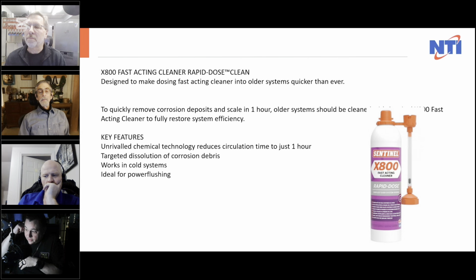The other thing, and this is a pet peeve of mine that I see more and more -- guys don't realize the TRX small models, the smaller step 1, the 85 to 150C boilers, have an internal filter on the right-hand side. So when you install the boiler, don't push it right up against the wall on that side; leave that area open so you can get the jacket off, because there's a filter right on the right-hand side of the pump, right at the pump inlet. I've pulled a lot of pump filters out and seen that filled up, and that will affect the flow.